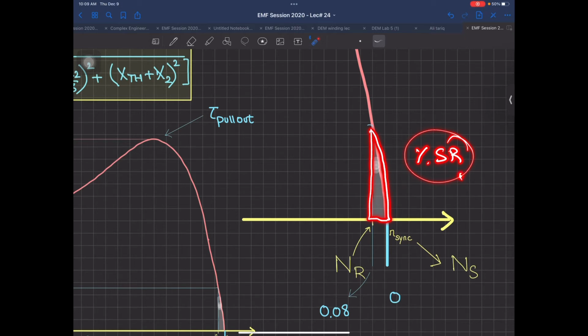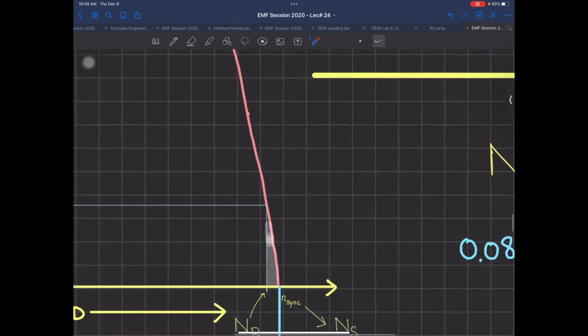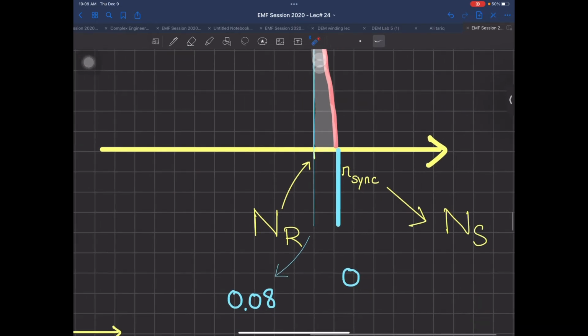Otherwise in DC machines, there were many machines where speed was decreasing as the load was increasing. Here the slip percentage, which is the maximum slip at full load, is not more than 8%, or in worst cases 10%, not more than that. But if you have done the experiment in your machines lab on DC machines, you would have found 25%, 30%, 40% even over there. But in induction machine, this is the region over here.